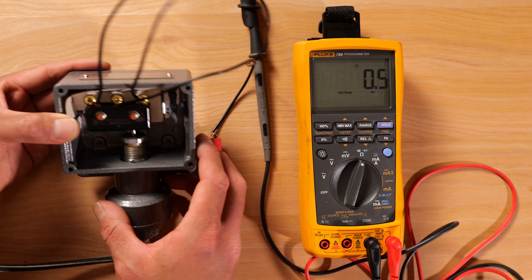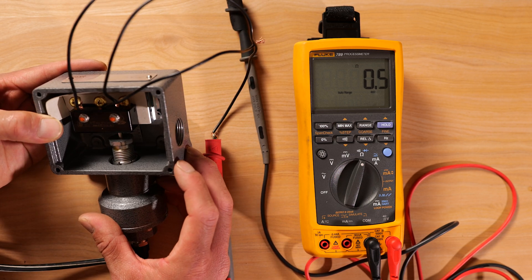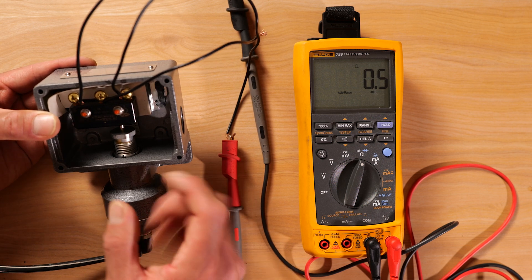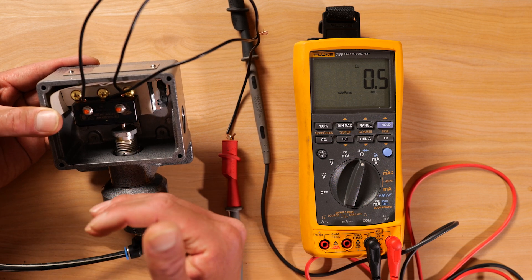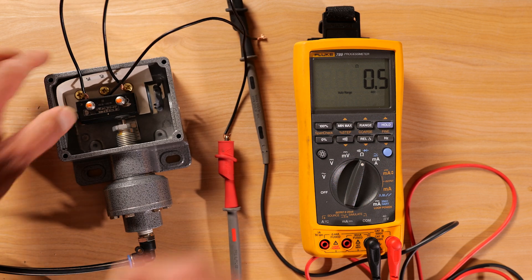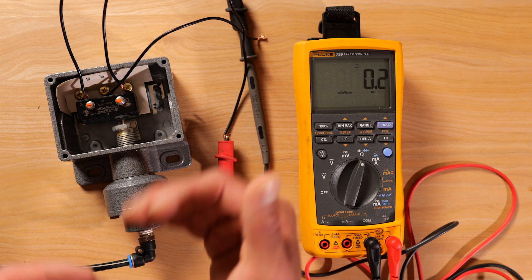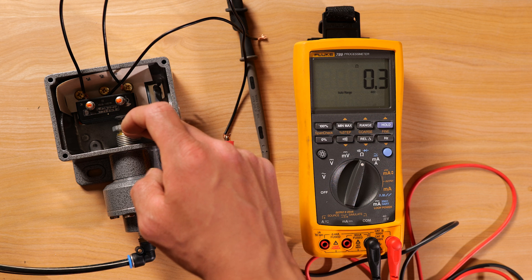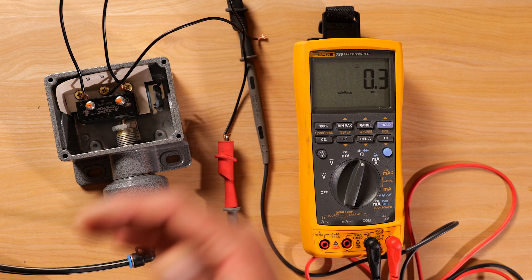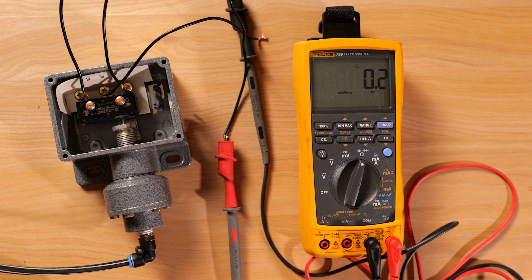So now I have it set at probably about 15 PSI. So with those few turns, we went up about 5 PSI. So then with the digital gauge or with any kind of gauge you have, you can then apply pressure on it and test it, go up and down, find the sweet spot and test it this way. So this is how you test a mechanical pressure switch.